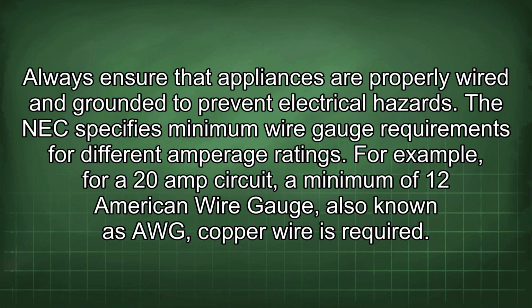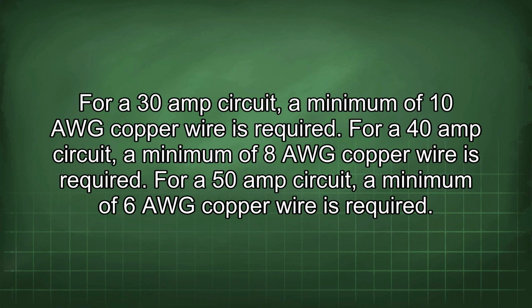The NEC specifies minimum wire gauge requirements for different amperage ratings. For example, for a 20 amp circuit, a minimum of 12 American wire gauge, also known as AWG, copper wire is required. For a 30 amp circuit, a minimum of 10 AWG copper wire is required. For a 40 amp circuit, a minimum of 8 AWG copper wire is required. For a 50 amp circuit, a minimum of 6 AWG copper wire is required.